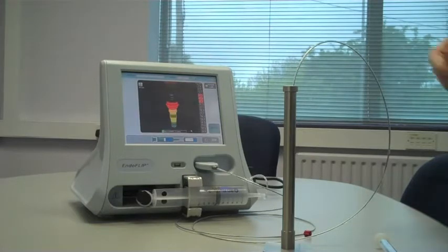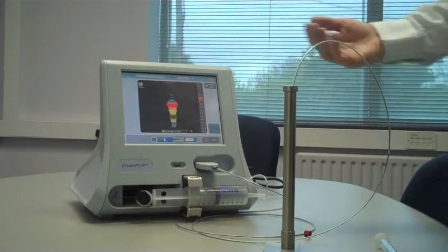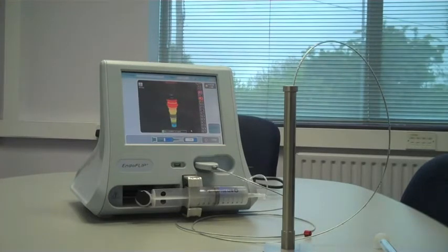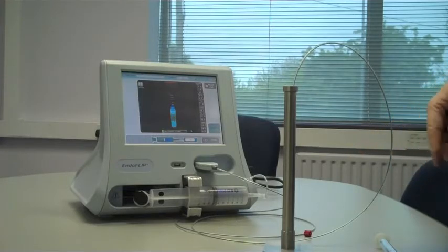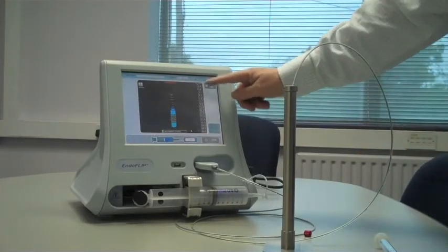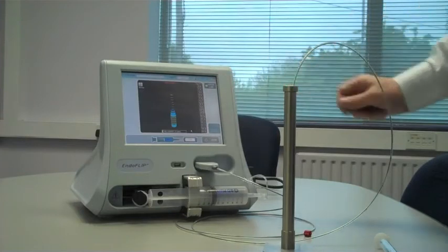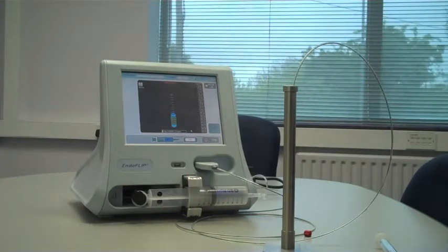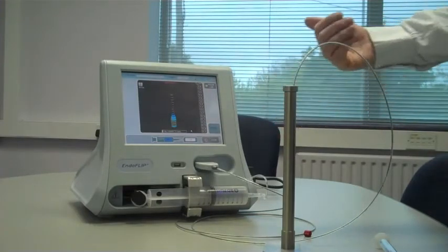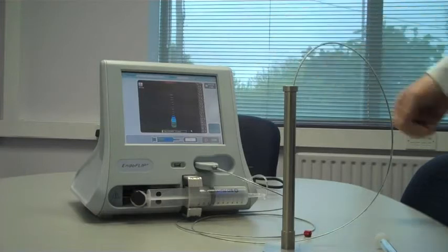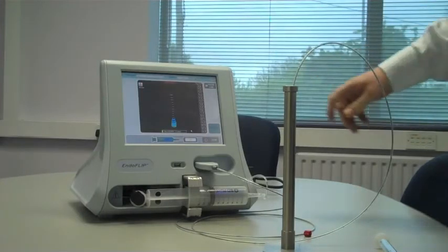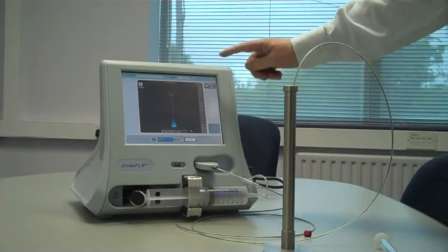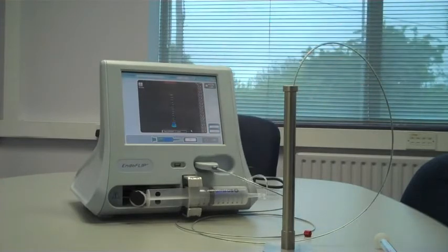The system is then going to withdraw saline and then re-infuse it into the balloon. And what we expect to see then is approximately 14 millimeters in diameter being measured at each electrode. So what's happening right now is that the system is withdrawing the fluid and it's going to pump it back in, and we should see approximately 14 millimeters on every catheter point.